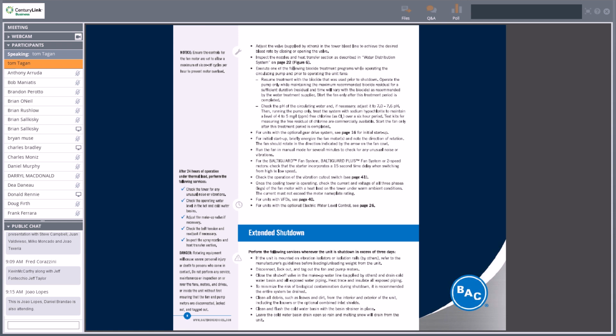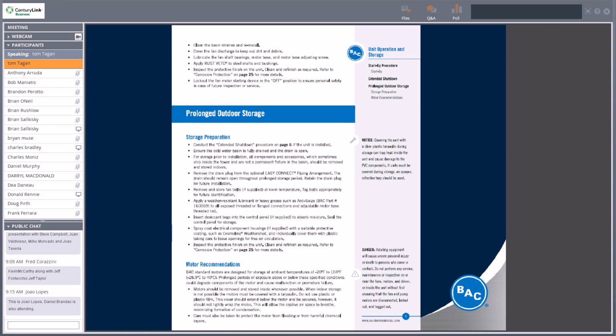You want to clean all debris from it, clean and flush the cold water basin and basin strainer in place, leave the cold water basin drain open so that rain and melting snow will drain from the unit. That way, if it was a heavy rainstorm or snow event, you're not going to get any freezing that could damage the basin. Again, it talks about cleaning the basin strainer, cover the fan discharge to keep out dirt and debris. That may not always be the case, but again, they're going to talk to you a little bit later on in the manual about cleaning the tower before you start it back up.